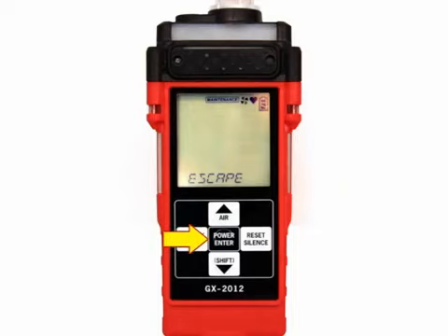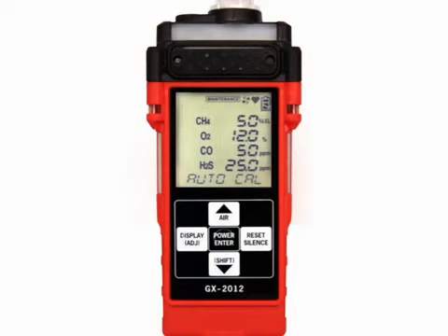Press and release the power enter button to return to the calibration gas value screens. Use the air or shift buttons to select which sensors you want to calibrate, the standard 4 or the percent volume combustible gas sensor, and press and release the power enter button.